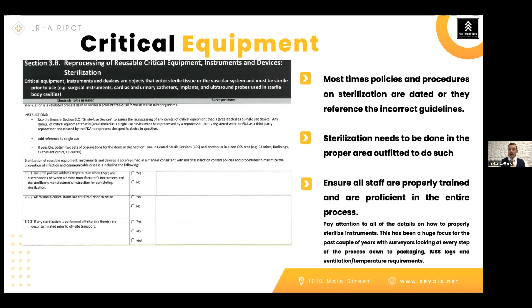Moving on for critical equipment, this is the biggest thing that you can do to start the process. Once the procedure is over, make sure that you pre-clean. Pre-cleaning is an absolute must. That is right at the bedside, making sure that for any instrument that you use in a procedure that you've done, we remove all gross soil on those items as close to the procedure and as soon after the procedure as possible. The reason for this is that bioburden can harden on these instruments, especially if you're using scopes with different lumens, or if you're using instruments that have a lot of blood or different body fluids on them. They can harden and they are extremely hard to get off, and that can cause you problems down the road. So pre-cleaning is an absolute must.